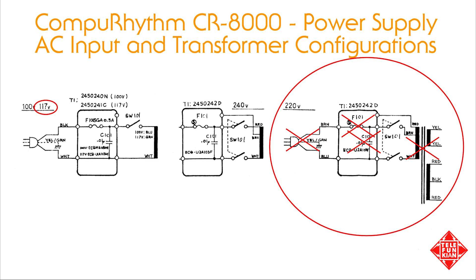After passing through the power transformer, the secondary outputs are connected to the CPU board. One secondary winding provides a nominal 10 volts AC at 700 milliamps that's regulated to provide the 5 volt DC supply for the CPU and logic circuitry. The other secondary provides 23 volts AC on each side of a center tap at 120 milliamps, which is regulated to plus or minus 15 volts DC to power the analog sound generation circuitry.